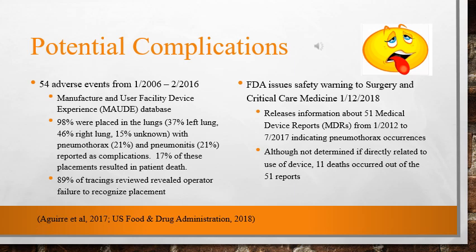So when this was investigated a little bit further, they identified that 89% of the tracings reviewed revealed that the operator failed to recognize correct placement. Okay, so they failed to see that they were actually in the wrong place 89% of the time of these 54 events.